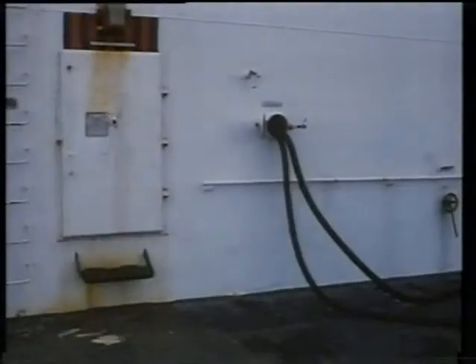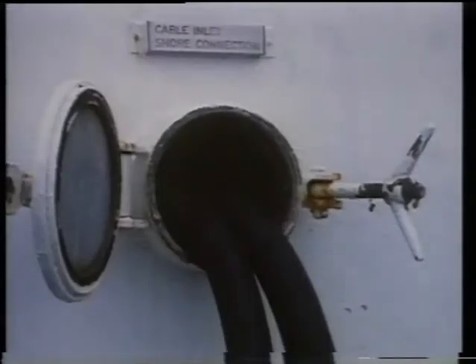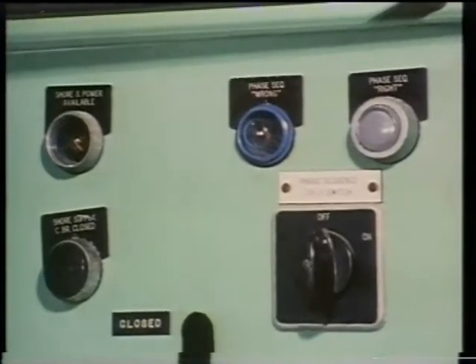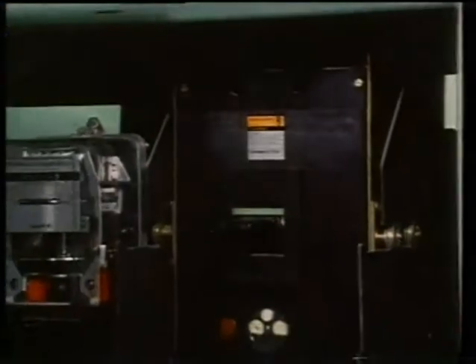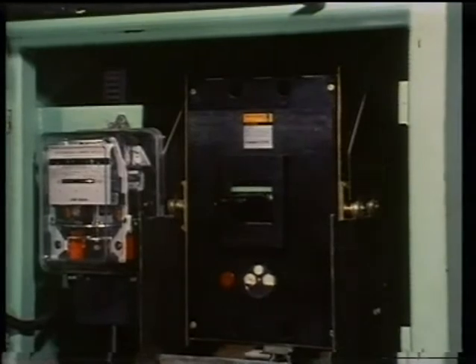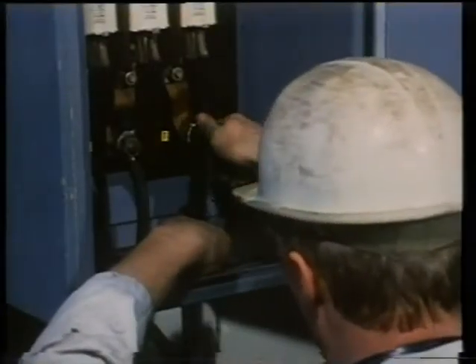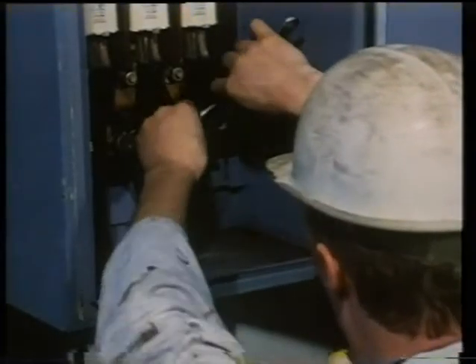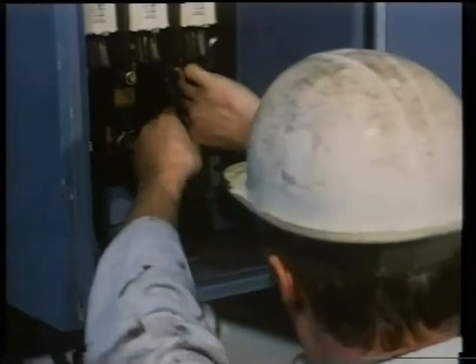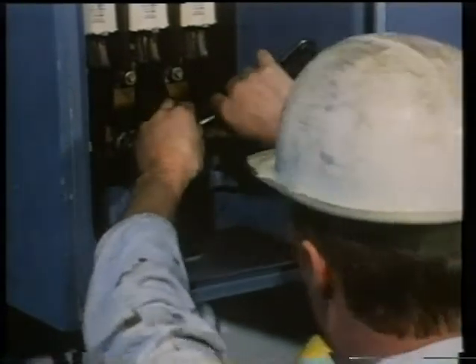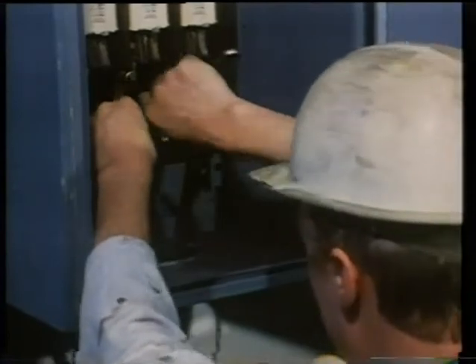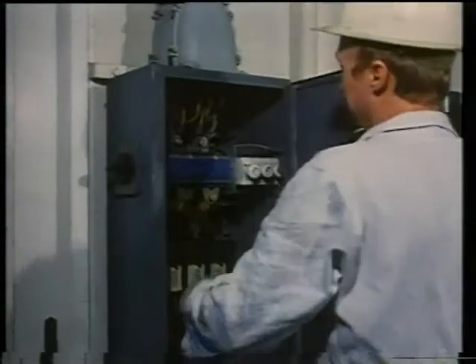When a vessel is in dry dock, mains power may be supplied from shore. Provision for connecting shore power to the ship's system is given either at the main switchboard or at the emergency switchboard via a circuit breaker. In some cases, a separate shore supply connection box is used, where the supply from shore can be connected near the deck area. A permanent connection will take the supply from the connection box to the appropriate switchboard.